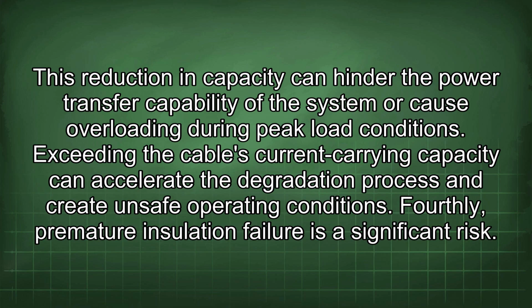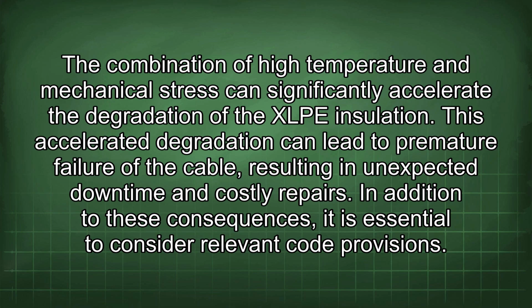Fourthly, premature insulation failure is a significant risk. The combination of high temperature and mechanical stress can significantly accelerate the degradation of the XLPE insulation. This accelerated degradation can lead to premature failure of the cable, resulting in unexpected downtime and costly repairs.